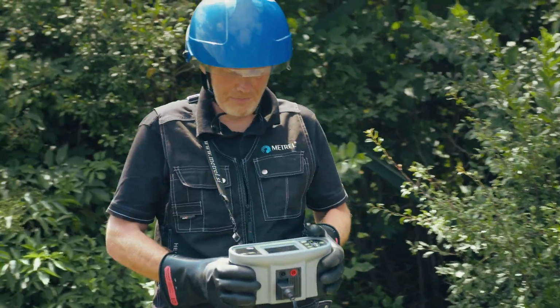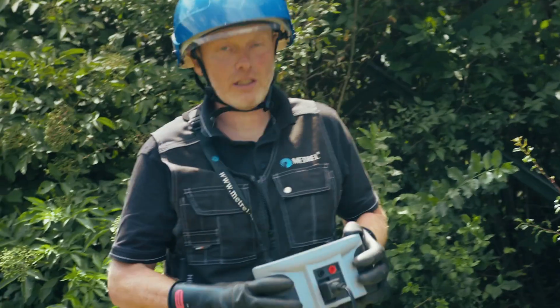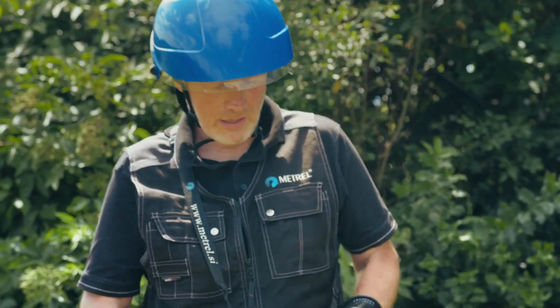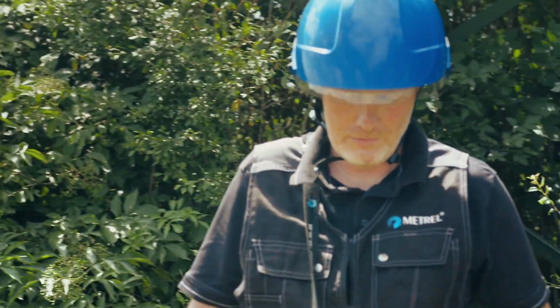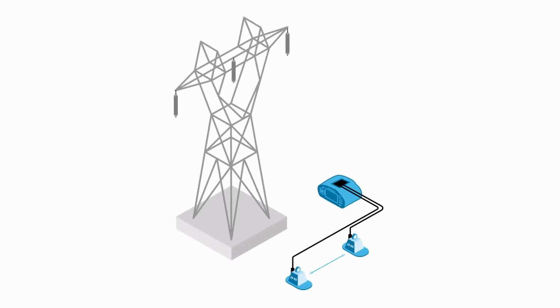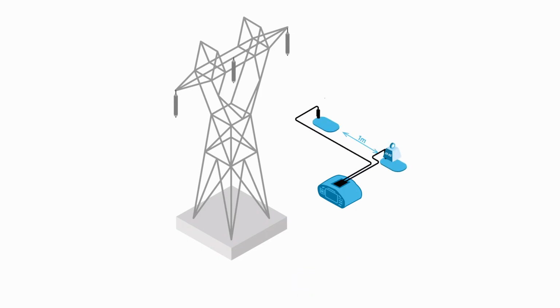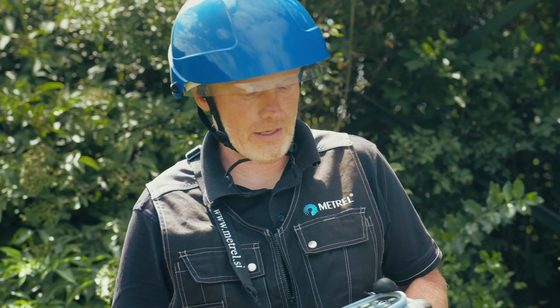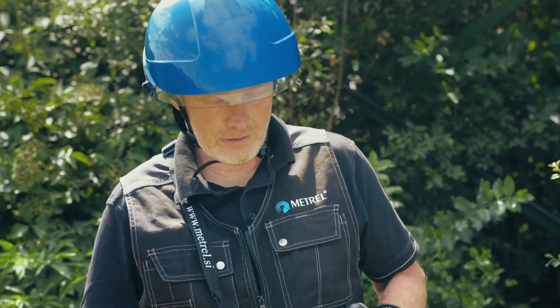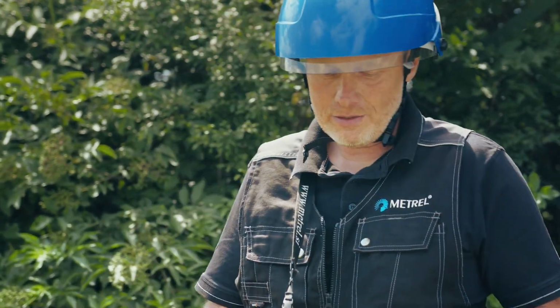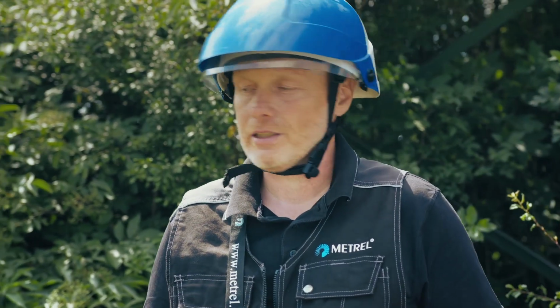Well, the last part, measuring of the step contacts in the surrounding, is the most time consuming for the measurements. We need to measure all around the pylon in different directions, 1 meter apart, 2 meters, 3 meters and so on, until we come to the safe area. Here, with these measurements, as we saw, the results are around 30 volts, which is very safe in this part.